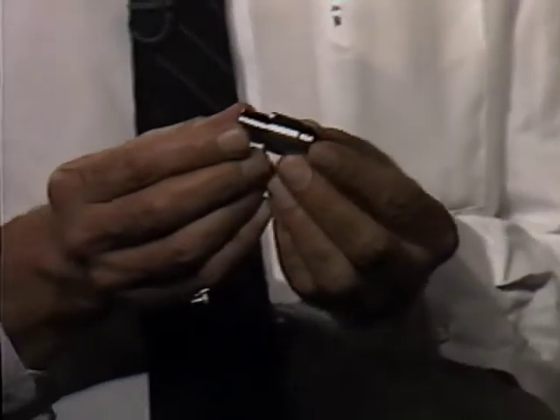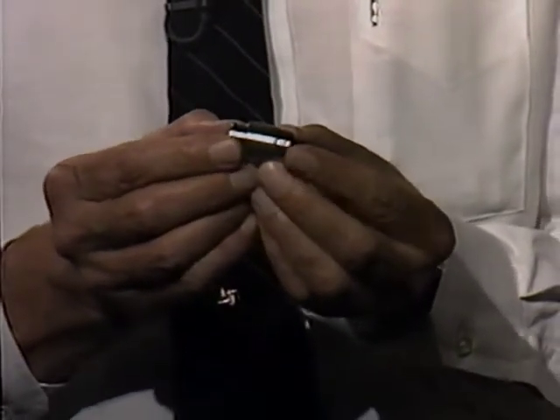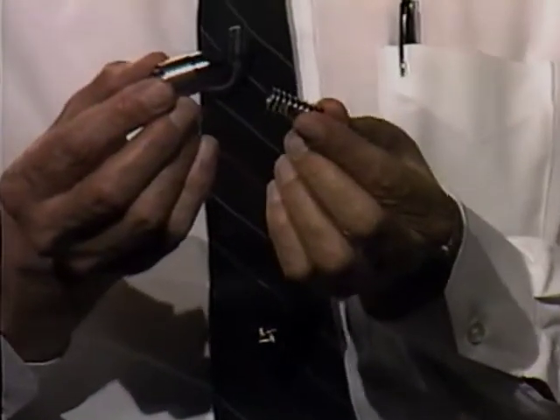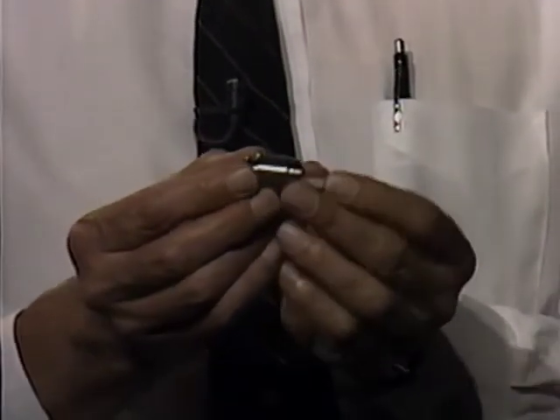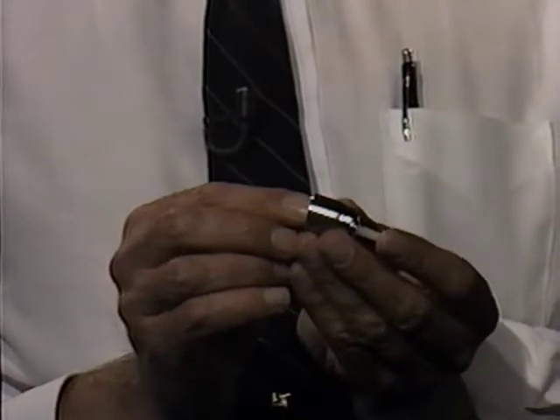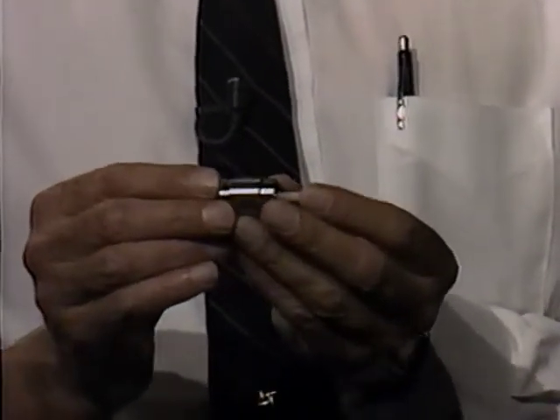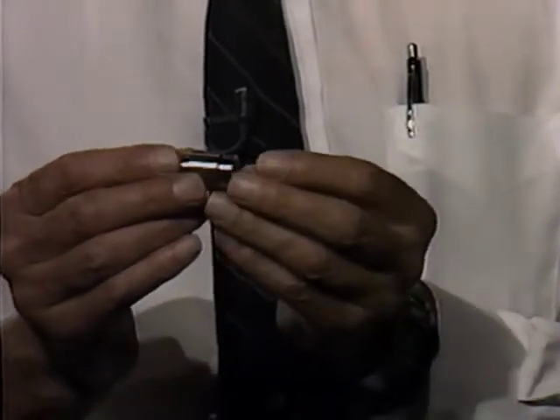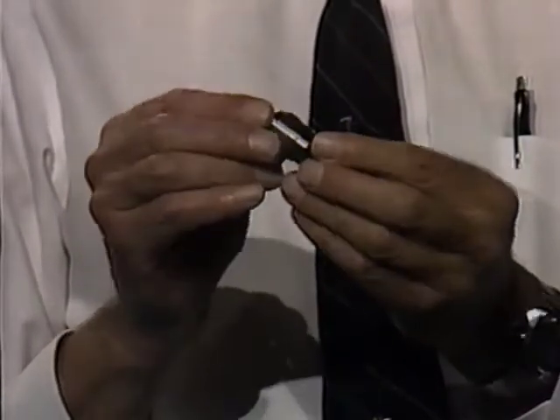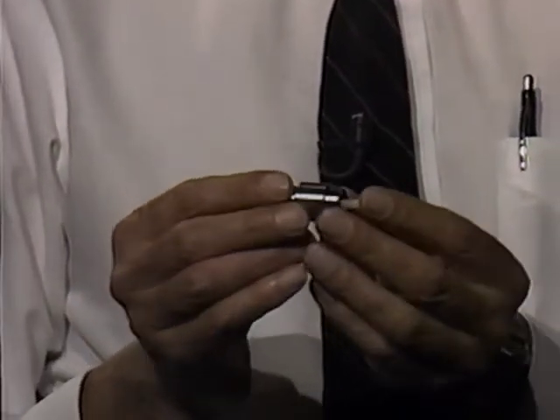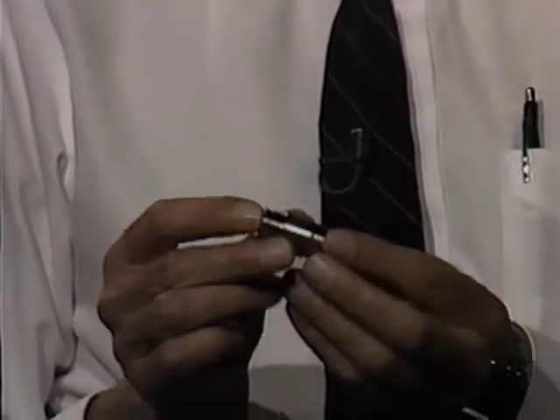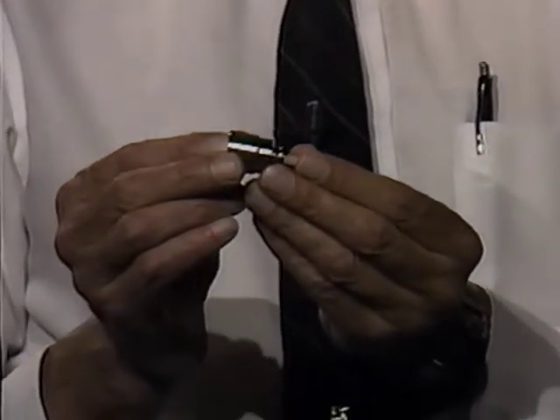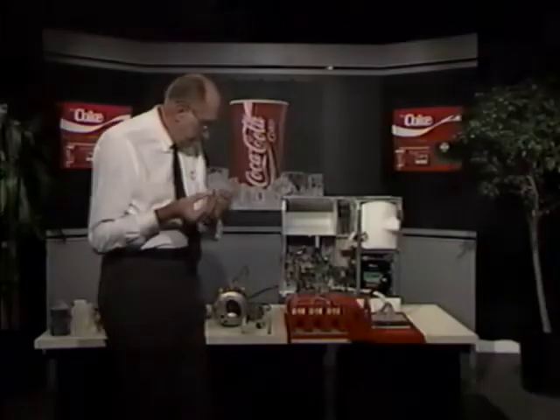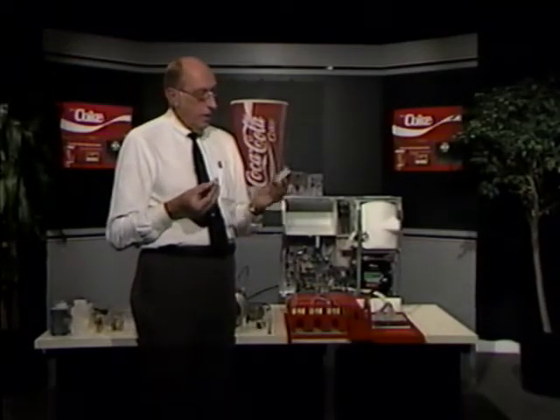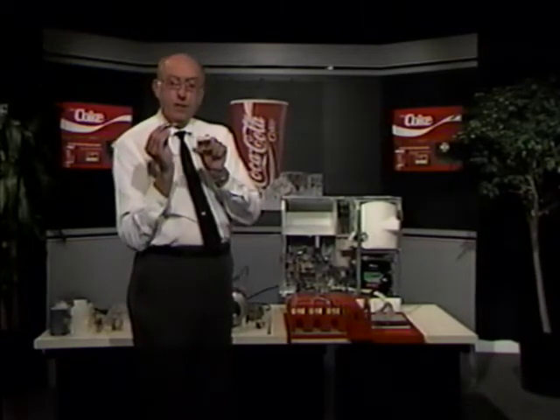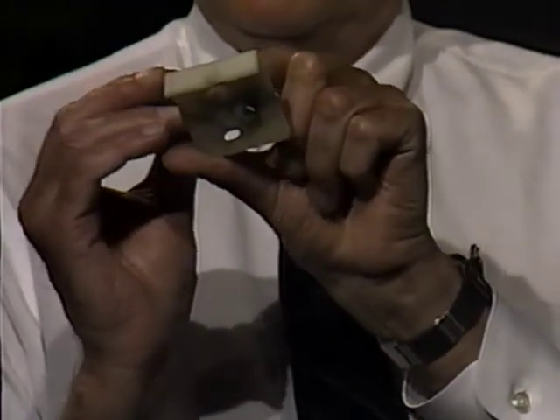We have a piston, stainless steel piston, and a stainless steel cylinder. And we have an operating spring to give us pressure against the cylinder. As the water flows in through the valve, it presses on the piston and pushes against the spring pressure. And the bottom of the piston will modulate the flow through these little tiny holes at the lower end of the cylinder. The spring pressure against the piston is adjustable through the adjusting screw, and you can adjust the flow rate simply by turning the adjusting screw. This is the adjusting screw operating against the push rod and the spring in the piston.